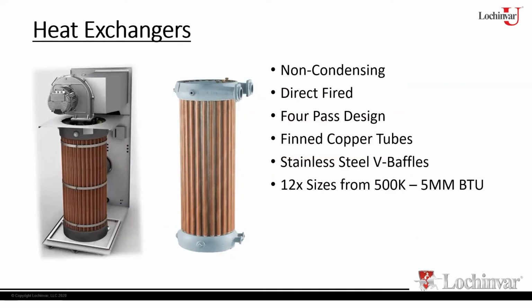The headers, we still go with cast iron headers, but here we've gone gasketless. With the original models, you had a gasketed top and bottom header. And as you know, if you've got a gasket in a heat exchanger, that is your weakest link. If there's going to be a leak, it would be at a gasket. So we've completely removed that. So we have a solid cast 1-piece headers, top and bottom.